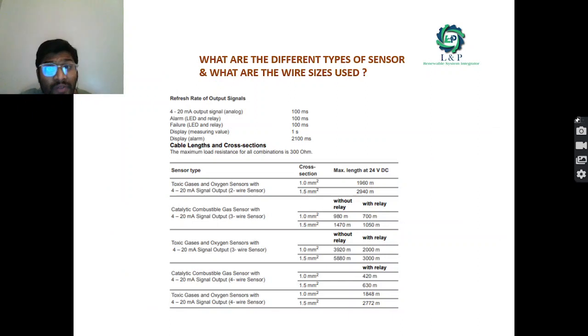And what are the different sorts of sensors, and what wire sizes can we use? As we told earlier, the analog output signal range is 100 ms, the alarm is also 100 ms, the display is 1 second, and the display alarm is 2100 ms. The maximum load resistance should be 300 ohms. The minimum cross-sectional area of the wire should be 1 square mm, and for a higher range, you can go with 1.5 square mm.